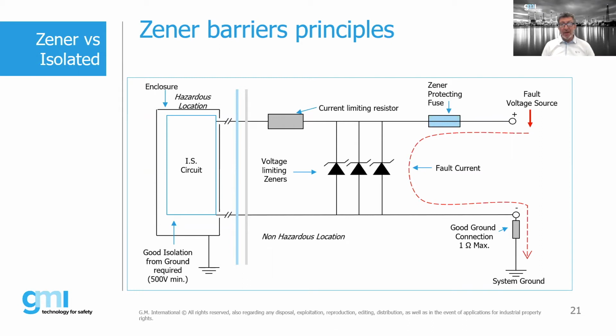It is something that GMI has always avoided, because if it's not certified for IA, and you use an IB in zone 0, you're not safe any longer. And we try to have the most stringent standard so that it fits in every application. But those are the differences. You're right. And as a manufacturer, I can tell you one other thing. These 3 diodes are tested individually before they are installed in the barrier. They're required to be tested.